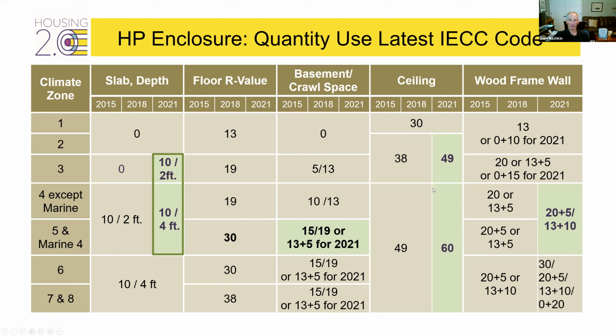For ceiling insulation, the attic insulation jumps from R-38 to R-49, and from R-49 to R-60 for colder climates. That seems rigorous, but if you're doing a raised heel truss, the 60 drops to 49, and if you're doing an unvented attic, the 49 drops to about 38. So 38 isn't too much insulation. These are the prescriptive numbers, which you can negotiate down using the overall U sub O calculation.